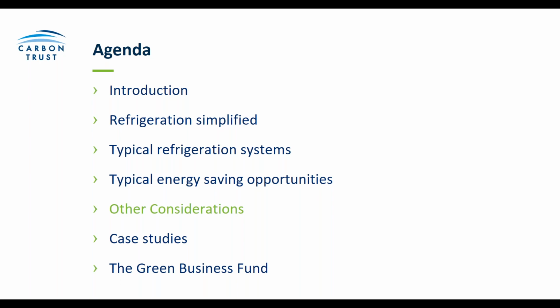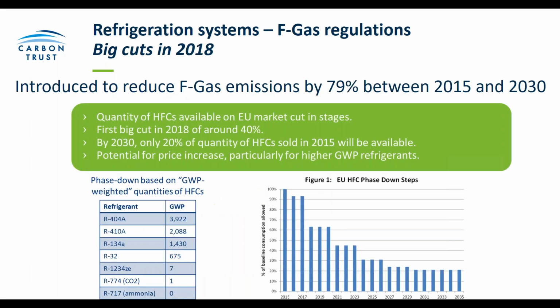This is mostly to do with regulation and legislation that has been and will be coming into play in the UK. In 2018, the quantity of HFCs, or hydrofluorocarbons, which are most commonly used as a refrigerant gas in your refrigeration systems, was to be reduced. So the availability of these on the EU market and in the UK generally would be reduced in this time. There's a general goal by the government to reduce the prevalence of HFCs in the UK by 79% between a baseline of 2015 and 2030. The first big cut happened in 2018, when about 40% of the HFCs on the market were cut out.